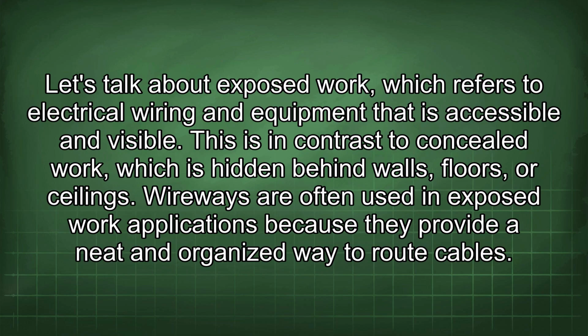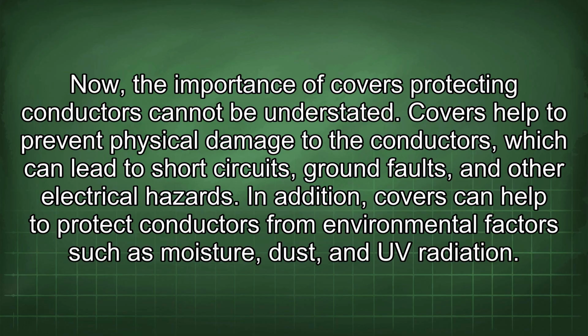Let's talk about exposed work, which refers to electrical wiring and equipment that is accessible and visible. This is in contrast to concealed work, which is hidden behind walls, floors, or ceilings. Wireways are often used in exposed work applications because they provide a neat and organized way to route cables. Now, the importance of covers protecting conductors cannot be understated. Covers help to prevent physical damage to the conductors, which can lead to short circuits, ground faults, and other electrical hazards. In addition, covers can help to protect conductors from environmental factors such as moisture, dust, and UV radiation.